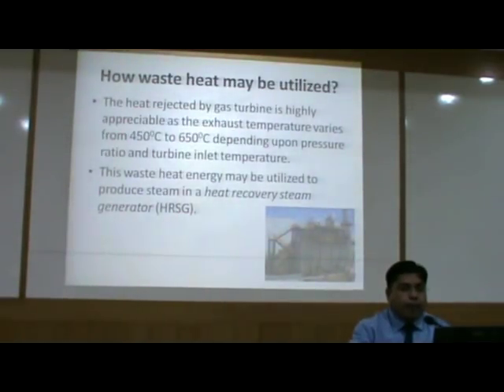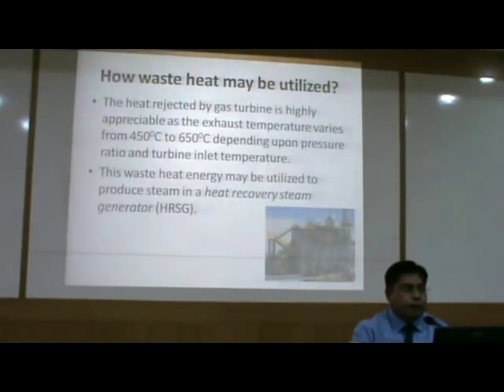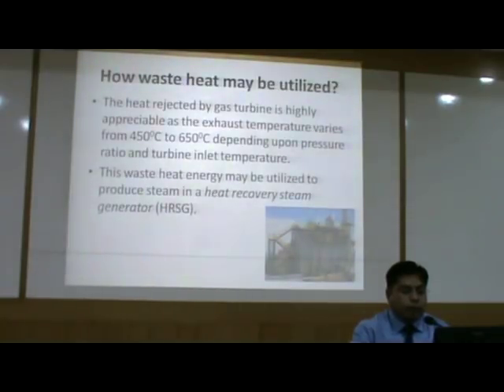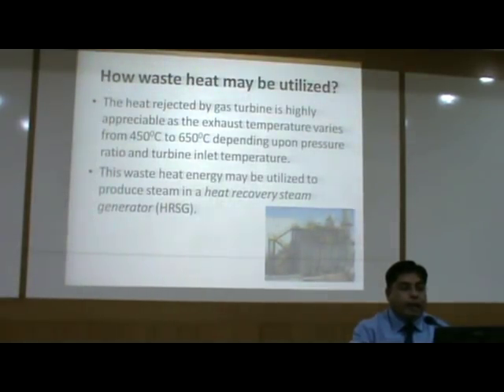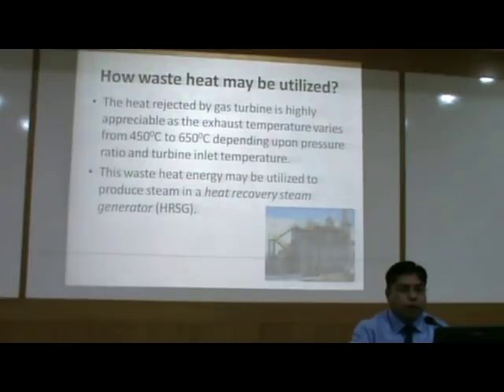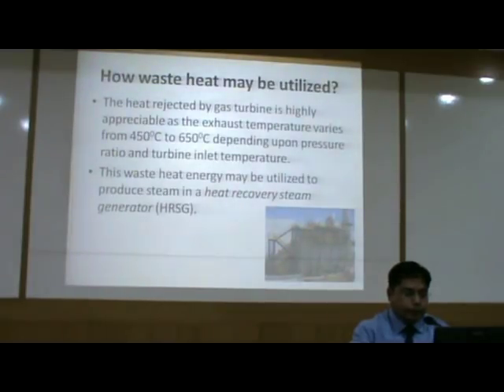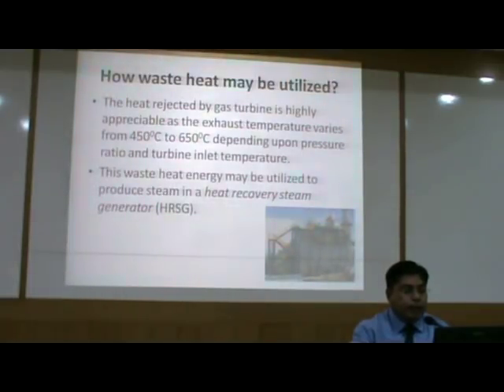The exhaust coming out of the gas turbine is at a temperature of nearly 600 degrees centigrade. The challenge is how such heat, which is going as waste in the exhaust, can be utilized. As the heat rejected by the gas turbine is highly appreciable — the exhaust temperature varies from 450 to 650 degrees centigrade depending upon pressure ratio and turbine inlet temperature — this waste energy may be utilized to produce steam in a heat recovery steam generator (HRSG).